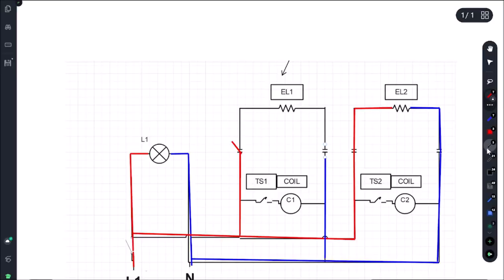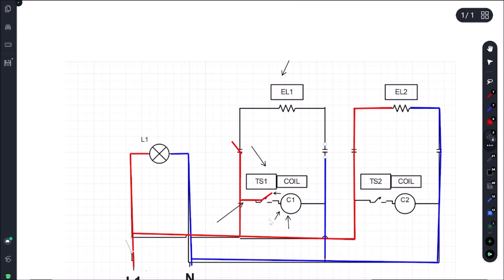As you can see, we had a bad thermostat. You can troubleshoot from two directions — either driving in from L1 or from the load working backwards. I like to go to the load and work backwards. When I tested at the coil I had no voltage, so I started working in that direction. We had power coming into the thermostat but nothing coming out — that means this bridge is open, so the fault is the thermostat. We confirmed it by testing potential difference across L1, getting 123–124 volts, confirming the switch is in fact open.